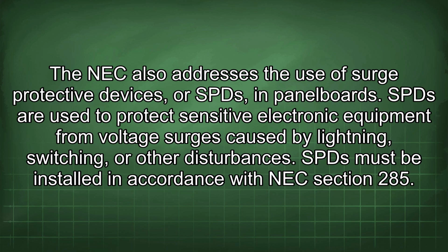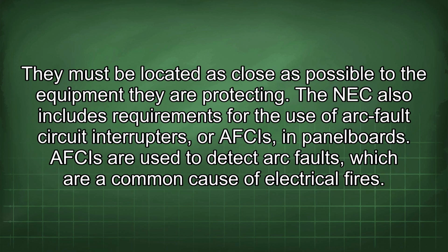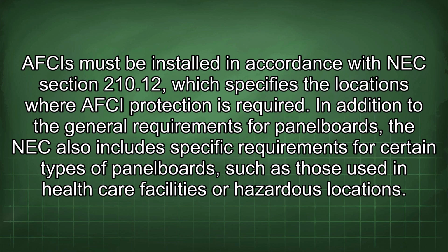The NEC also addresses the use of surge protective devices, or SPDs, in panel boards. SPDs are used to protect sensitive electronic equipment from voltage surges caused by lightning, switching, or other disturbances. SPDs must be installed in accordance with NEC section 285. They must be located as close as possible to the equipment they are protecting. The NEC also includes requirements for the use of arc fault circuit interrupters, or AFCIs, in panel boards. AFCIs are used to detect arc faults, which are a common cause of electrical fires. AFCIs must be installed in accordance with NEC section 210.12, which specifies the locations where AFCI protection is required.